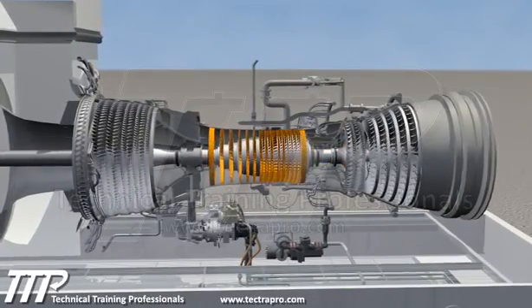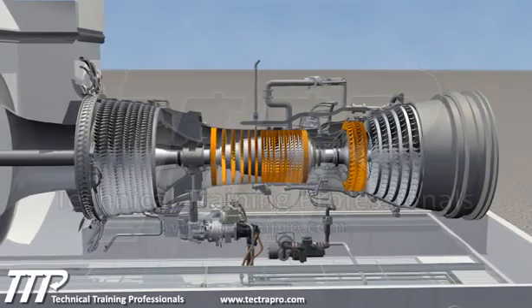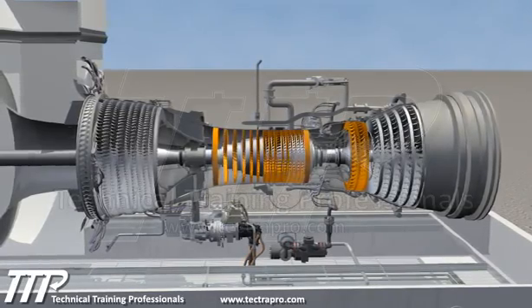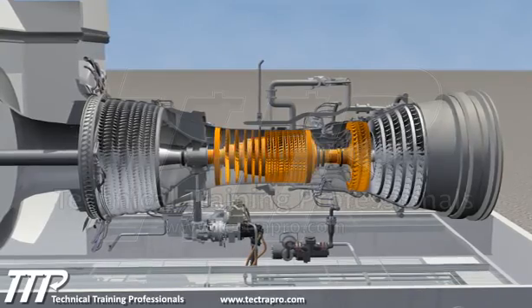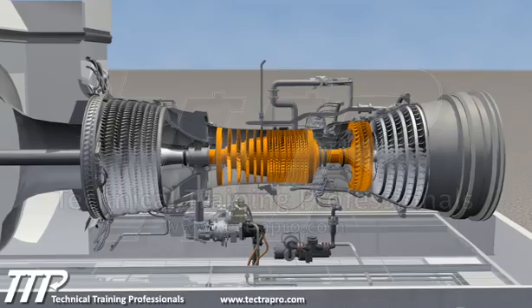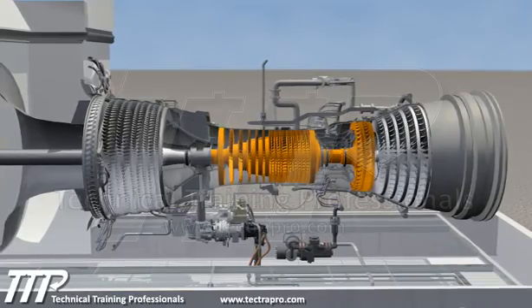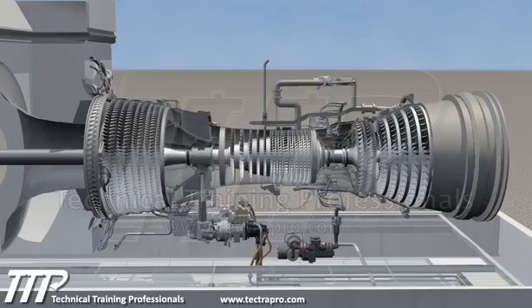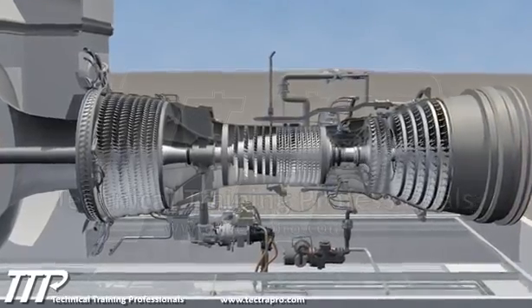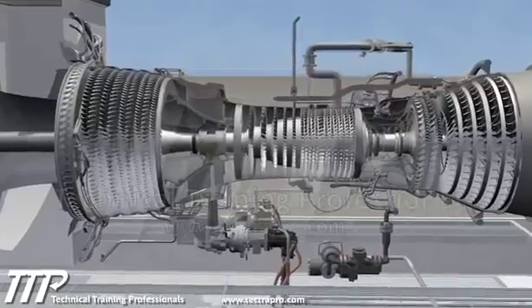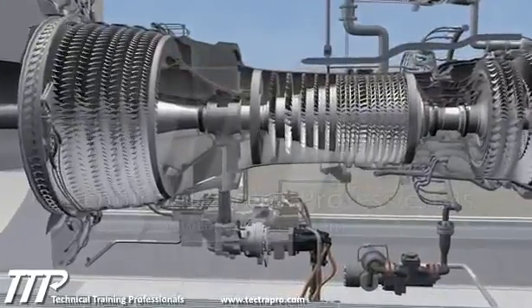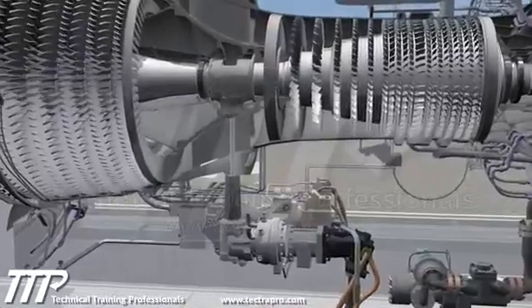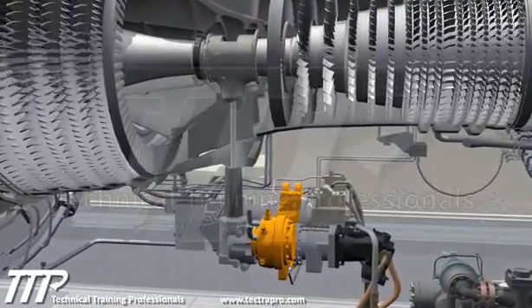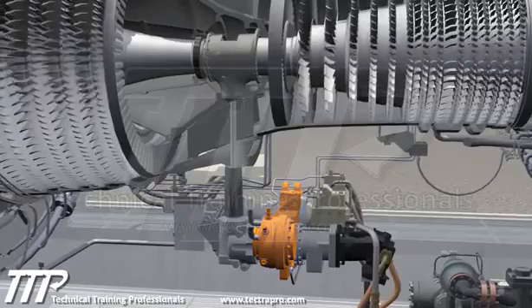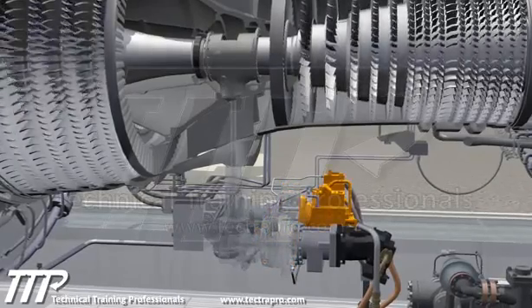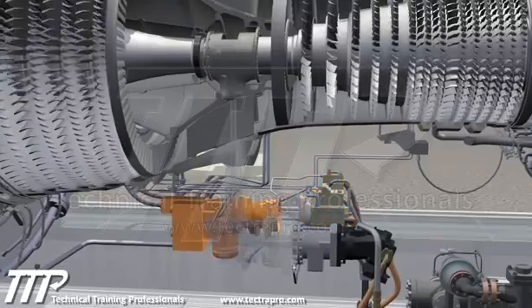The high-pressure compressor and high-pressure turbine are located between the low-pressure sections and connected by the outer rotor of the machine. The high-pressure system rotates at 10,350 RPM. The accessory's motive force is provided from the high-pressure rotor.